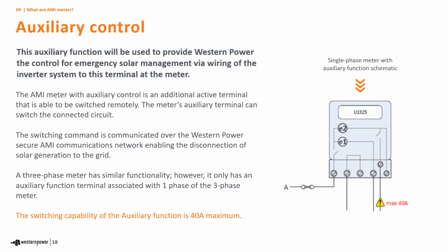We talked about auxiliary control terminals. This auxiliary function will be used to provide Western Power the control for emergency solar management via wiring of the inverter system to this terminal at the meter. An AMI meter with auxiliary control has an additional active terminal that is able to be switched remotely. The meter's auxiliary terminal can switch the connected circuit. We communicate that switching command over the secure communications network, enabling the disconnection of solar generation to the grid.